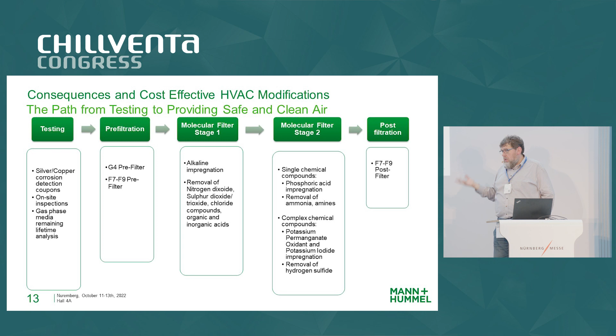And the chemical filters are basically simple, known, operating since decades, filters that are not just activated carbon, as a lot of people say. These have to be chemically impregnated filters that form a chemical reaction and solidify whatever gas you have onto their surface, so that you basically take out the pollutant and make it chemically totally unreactive. So this is the key point. And that means you usually, even with the continuous testing, need pre-filters to protect the activated carbon from dust. You go with specific filters for alkaline impregnation, with acidic impregnation to remove, for instance, ammonia and similar compounds. And then in order to prevent the carbon dust from going into your room air, you need a post filter.